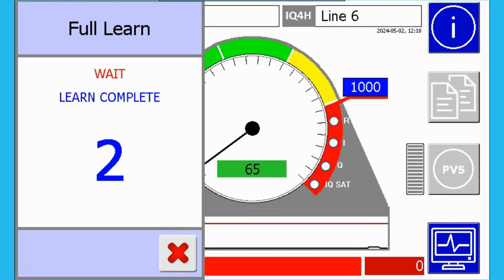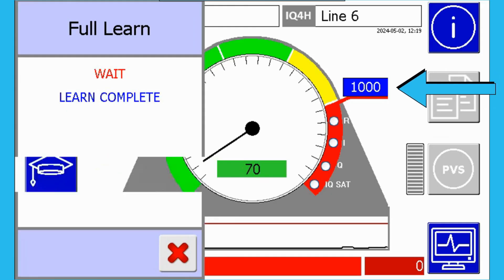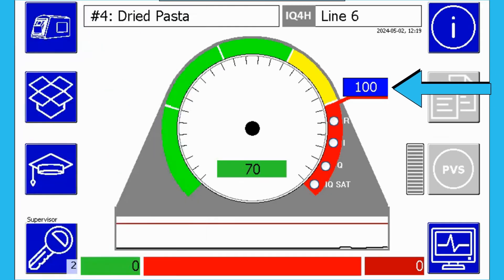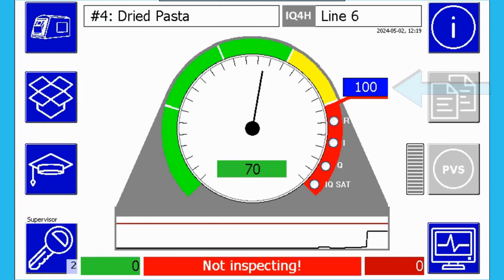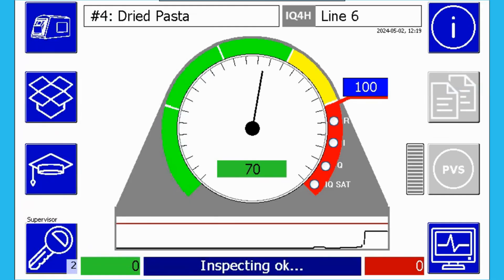And when the learn is complete, notice that the threshold will be set automatically to a low value, which can allow for better detection of smaller metal contaminants.